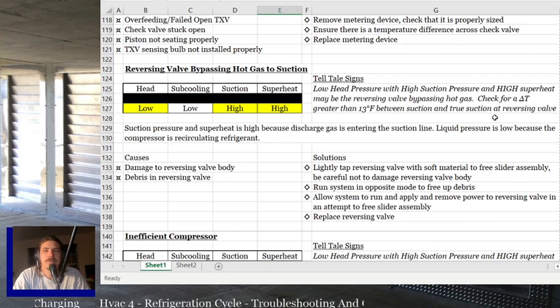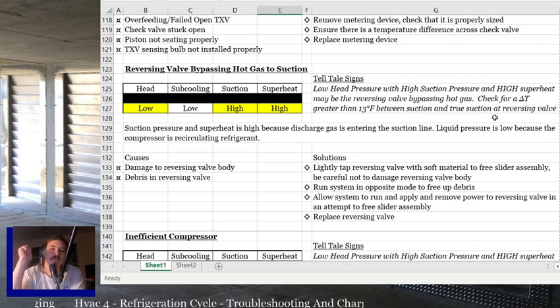Run the system in the opposite mode to try and free up debris. The next one is to allow the system to run and apply and remove power to the reversing valve in an attempt to free the slider assembly. So while the system's off, you can take the O terminal and just apply red to it on and off. You know what I mean? Jump it, not jump it, jump it, not jump it. Get that slider to try and move back and forth really quick.